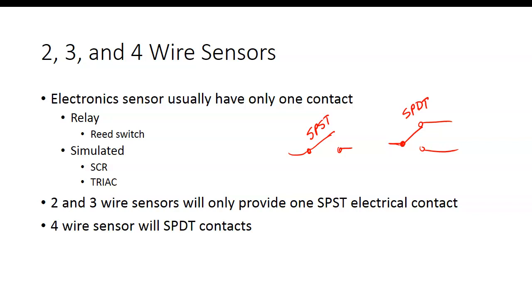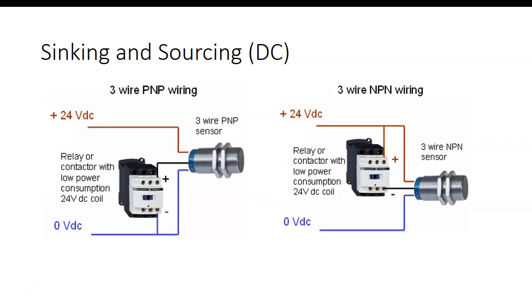So this is the control relay. How many contacts is that? I think 7 or 8. So what we can do is use the sensor to energize that relay, and we get a lot of contacts. So how many poles would that have? That would have 8 poles. So relays are rated by poles too, that's the number of actual contacts. So this is important to know.